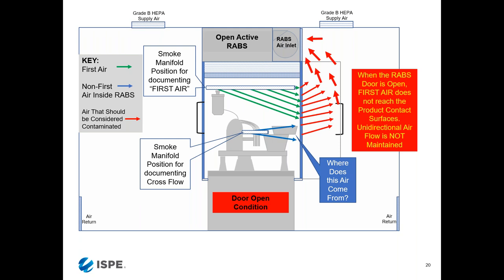If you look here, this is a manifold, near the stopper bowl. There is air going this way. There's air from the HEPA filter, top green, but there's air. Where is this air coming from? That means this is not a sealed enclosure. These are things that the regulators have started seeing now.